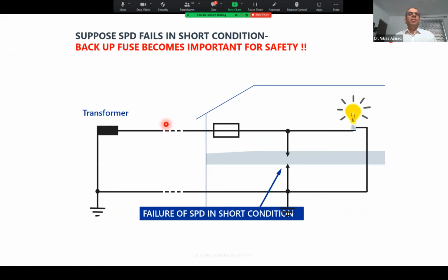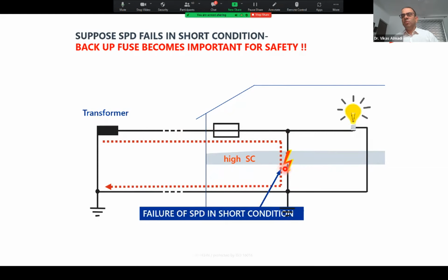Now, one more phenomenon. Let us say we are talking about the services here. And when we are talking about the services, we have to talk about the continuity of the services. And let us say this is the service we are providing, and this is the SPD, any type of SPD. During lightning, suppose there is a lightning strike, this will switch on, and while the SPD is on, there will be a huge current that will flow through the SPD, a huge short circuit current, depending upon the transformer, the distance of the transformer, etc. So the short circuit rating of the SPD, not only the 10/350 rating of the SPD, has also to be seen, and at the main entry level, it has to match with the other switchgear ratings in that panel.